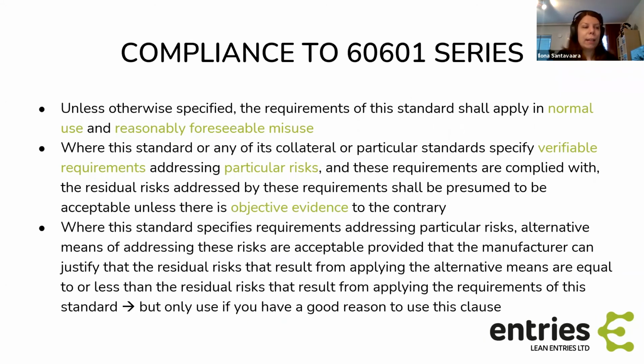And unless it's otherwise specified, requirements apply in normal use and in reasonably foreseeable misuse. And if there are, in the standard or any of the particular or collateral standards, verifiable requirements that address particular risks, so if they have, for example, a test for a certain mechanical hazard, and you have complied with this standard and the test result is okay, then you can assume that it's okay unless there is some objective evidence to the contrary. So you don't need to think about that any further.